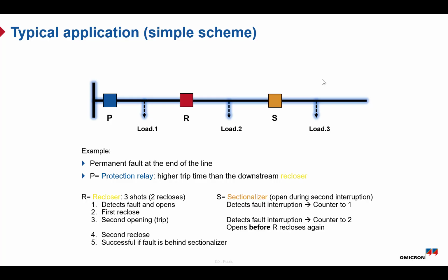If a fault happens near the end of the line, all protection devices will detect the fault and pick up, typically through overcurrent. However, we always want the device closest to the fault to isolate it. Since the sectionalizer cannot interrupt the fault current, the upstream recloser will trip first. The sectionalizer detects that a fault occurred and starts counting the number of interruptions. After the first trip, the recloser will attempt to close again in case the fault was temporary. If the fault is still there, the recloser trips again and the sectionalizer counts another operation.